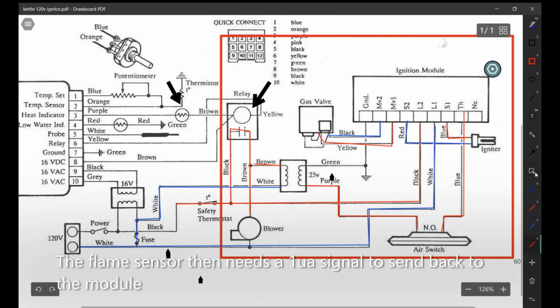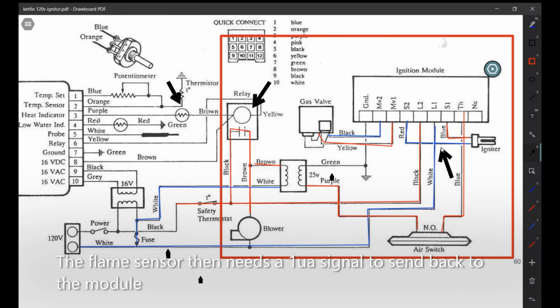And then we're looking for 1 microamp on the flame sensor, which is part of the igniter. It is polarity sensitive, so if you reverse this, you will never get any flame sense. Once we get flame sense, the igniter will then turn off at that point.